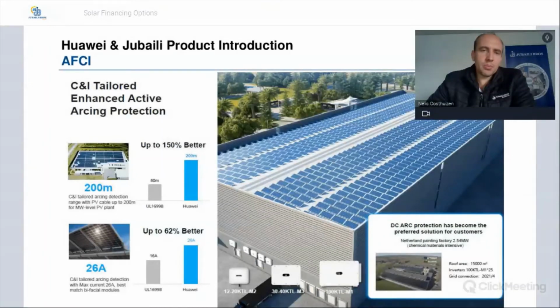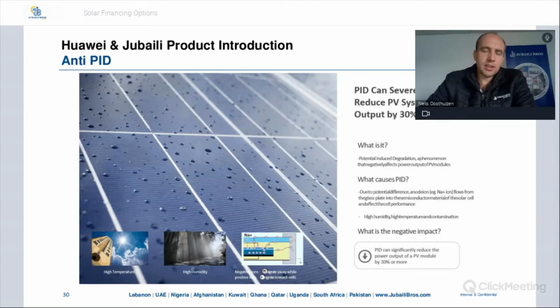Arcing can be caused by something as simple as a loose connection on your system. It can be where you've got damage on your PV cable, and your PV cable might be shorting to a cable tray or something. So these are all very simple possibilities for AFCI, but it happens a lot in real-time solutions out there. Then the next feature that's built into Huawei inverters is anti-PID.